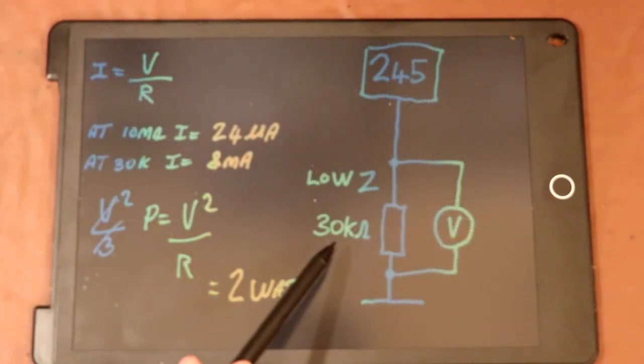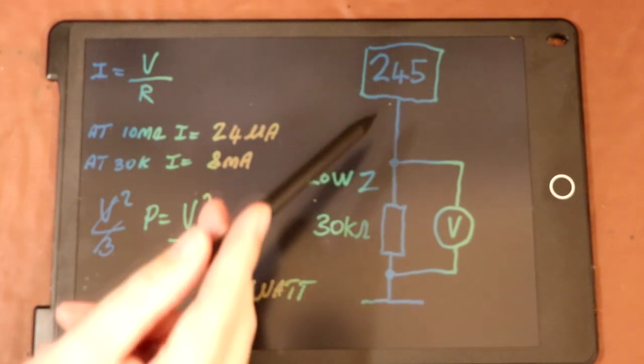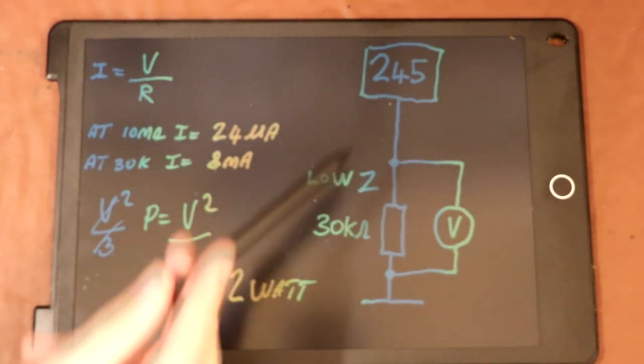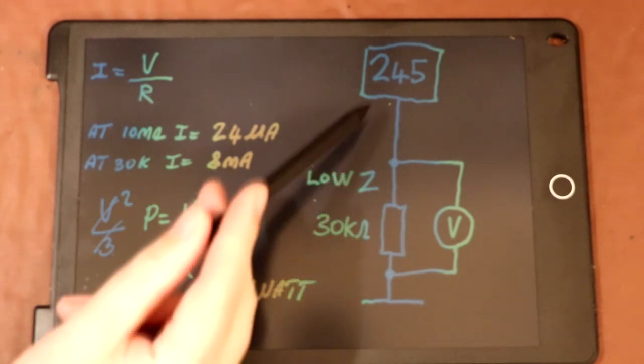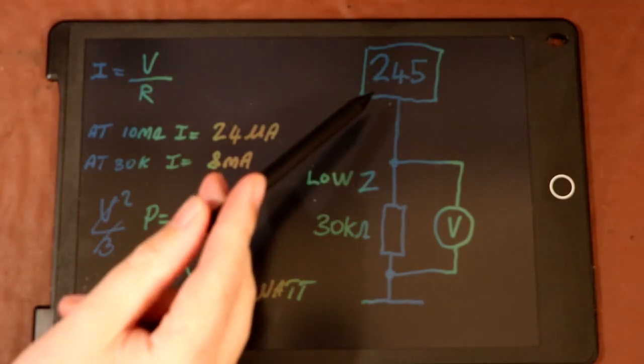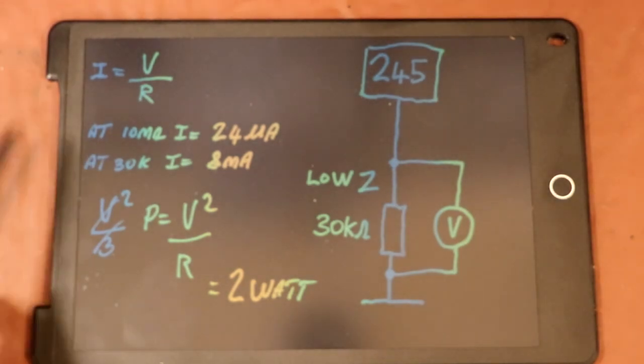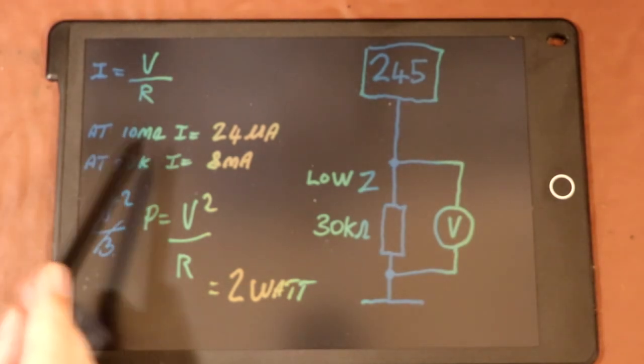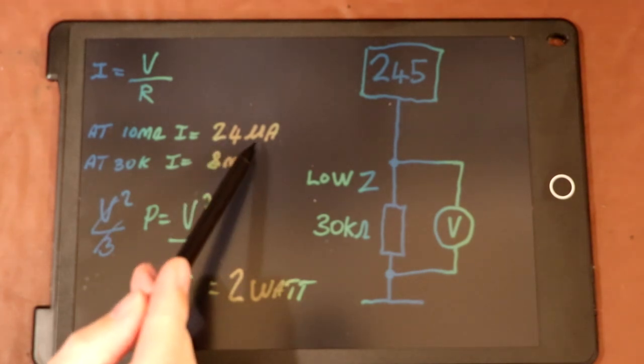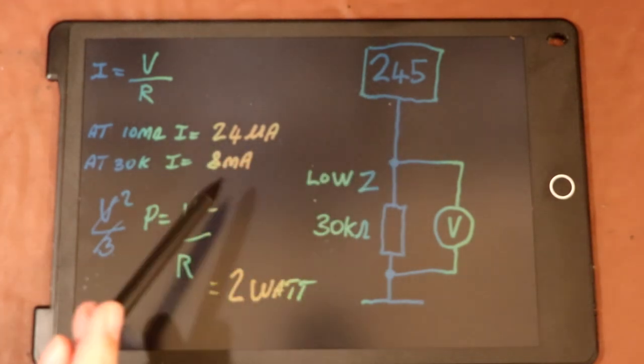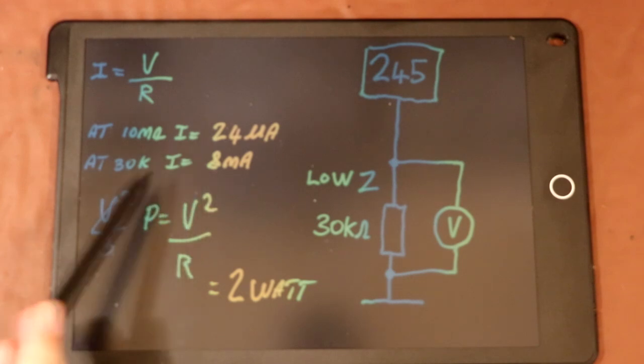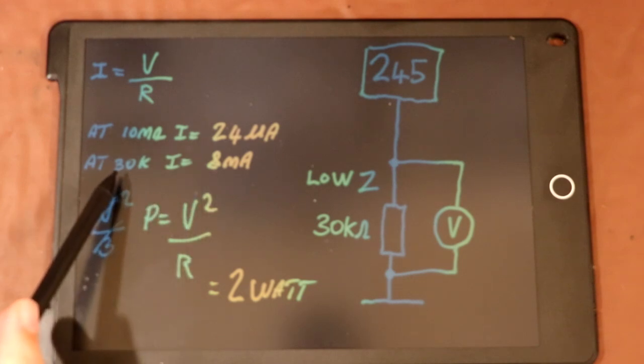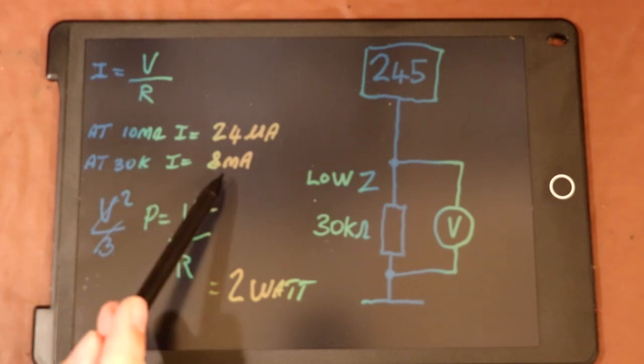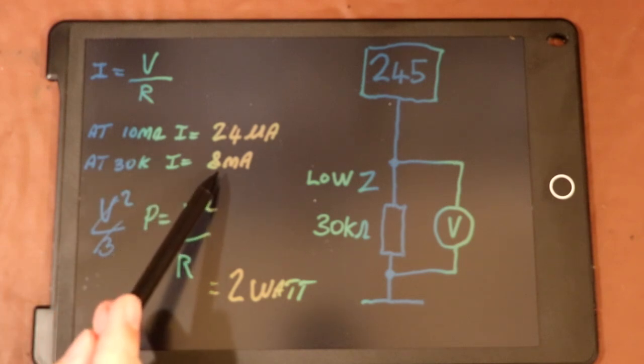When using the low Z function, the input impedance of the meter won't be its standard 10 megohms, it will be around 30 kiloohms. What that means is there'll be a lot more current flowing in your circuit when you're taking your measurement. In the case of a 245 volt supply, we can simply do Ohm's law. For a 10 megohm input impedance, we'd have 24 microamps of current flowing in circuit. But when we have the low Z measurement selected, because we've got 30 kiloohms rather than 10 megohms, the actual current flowing in the circuit will be 8 milliamps. So that's an awful lot more current.